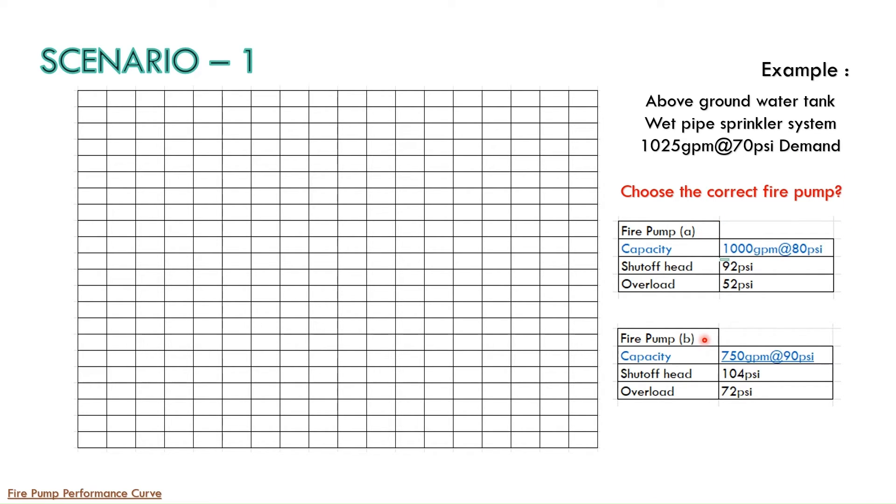So based on these data we need to select the fire pump. We have two options here fire pump A and fire pump B. Fire pump A capacity is 1000 GPM at 80 PSI and fire pump B capacity is 750 GPM at 90 PSI. So we need to draw the performance curve then only we will be able to select the correct fire pump. So we will consider the first option right now in this particular slide and draw the performance graph. So on x-axis we will put the flow in GPM and on y-axis we will put the pressure in PSI.